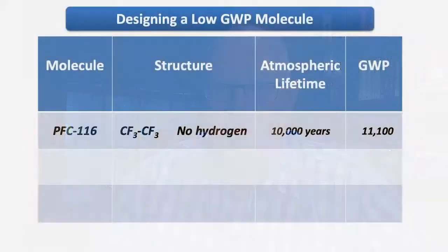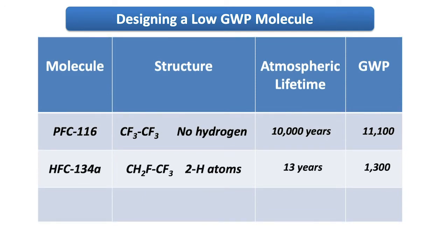I want to put a few examples here to illustrate how our choice of chemistry and refrigerants can really determine the atmospheric lifetime and GWP. If we take a molecule with only fluorine on carbon and no hydrogen at all — something like C2F6, hexafluoroethane — it has no hydrogen, so there's no hydroxyl radical destruction mechanism, giving very long atmospheric lifetimes and very high GWP. Now if we take a very similar molecule but substitute a few hydrogens for some of the fluorine, we get something like HFC-134a. It's very susceptible to hydroxyl radicals, has much shorter atmospheric lifetimes, and a lower GWP.